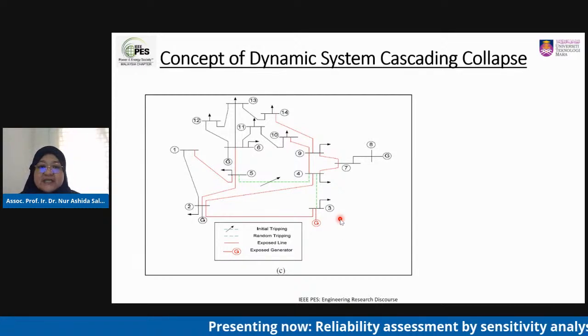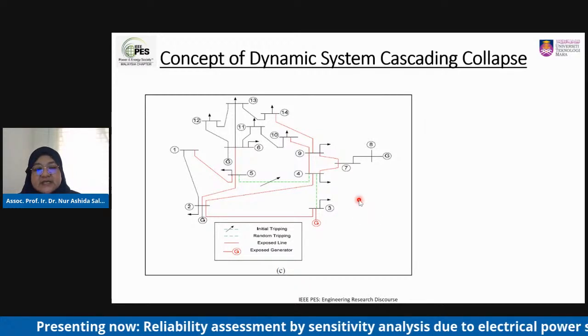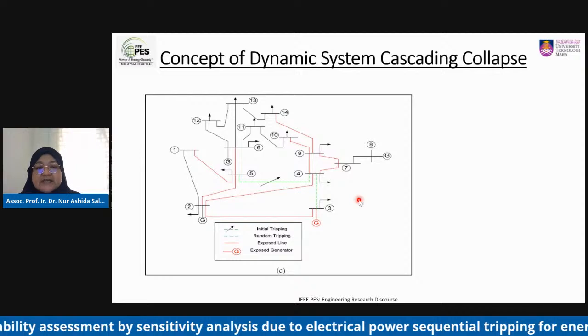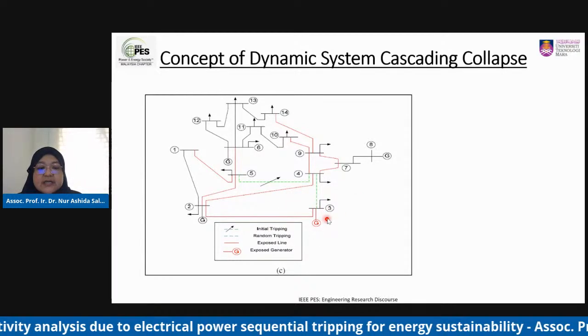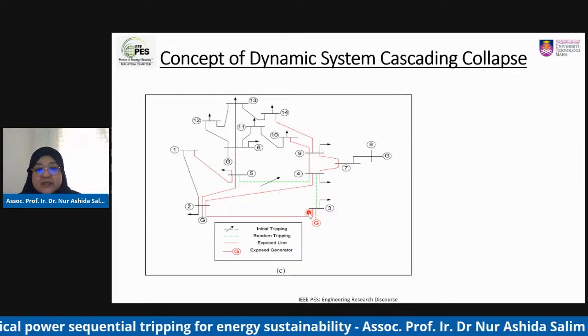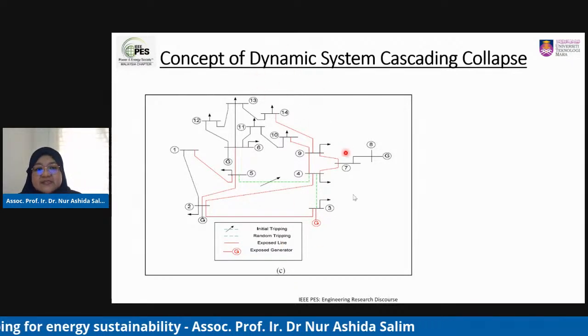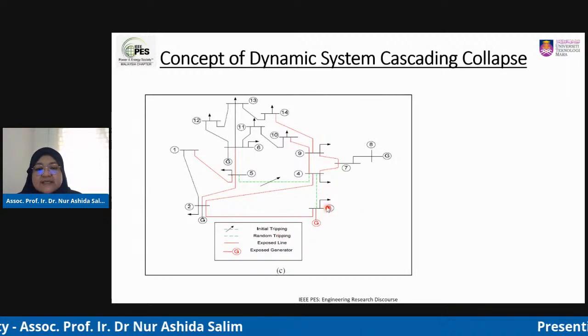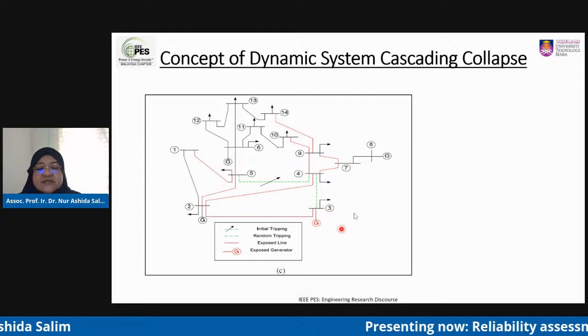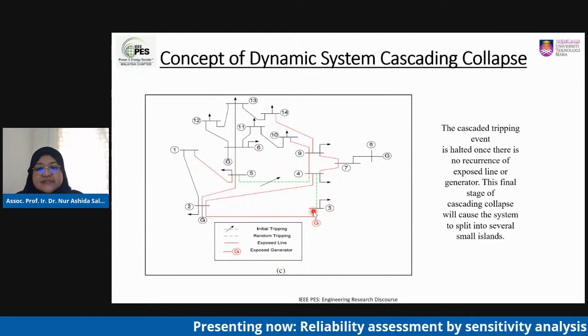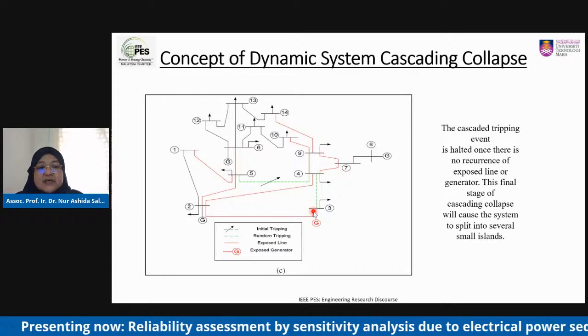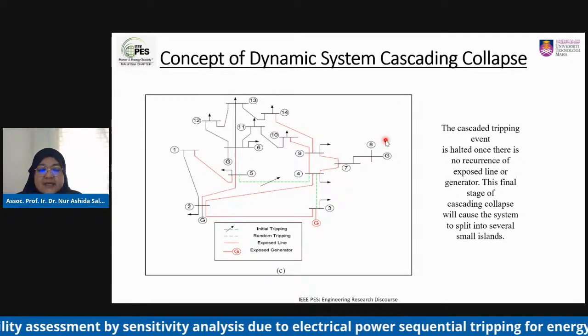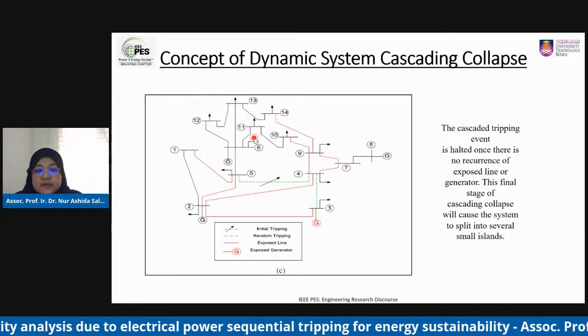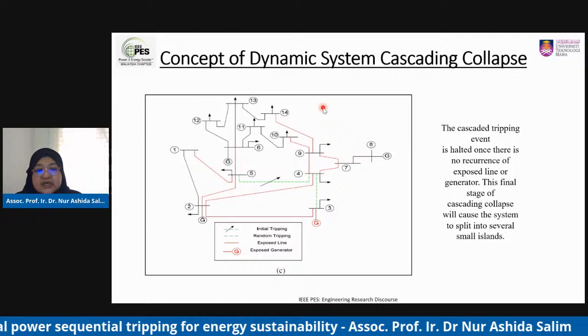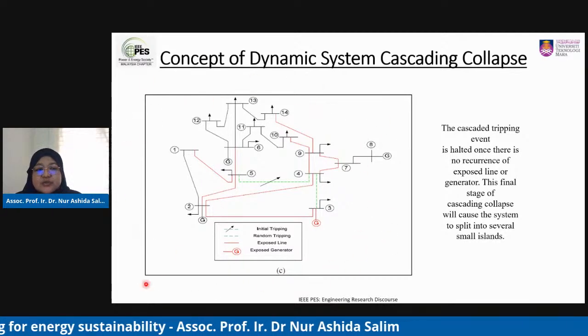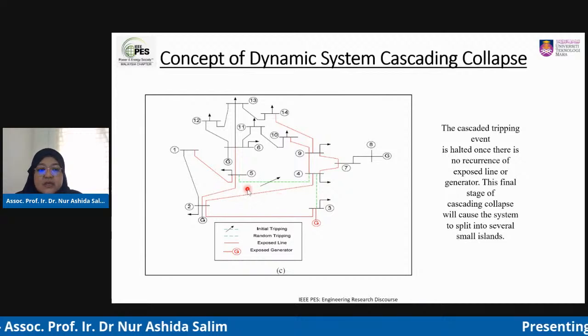Okay, so the difference between static and dynamic system cascading collapse is basically that in static, we only consider transmission line tripping, whereas dynamic system cascading collapse also involves generator tripping. When we deal with dynamic system cascading collapse, the analysis is a bit tedious, where we have to take into consideration the generator response. Same as in static system cascading collapse, when we want to know whether the cascaded tripping has stopped, it is due to two conditions: whether the whole system collapsed, I mean it is a total blackout, or there is no more tripping.